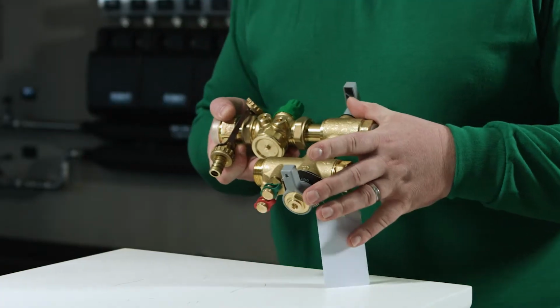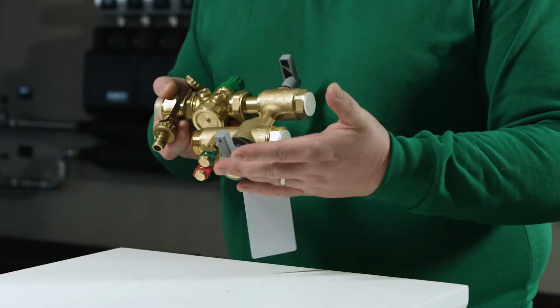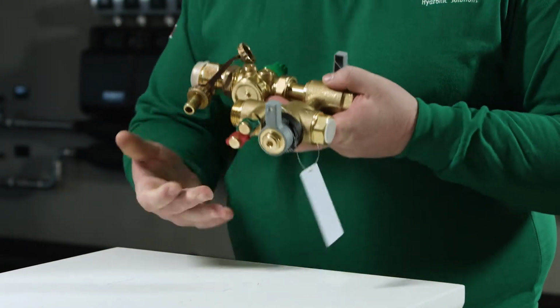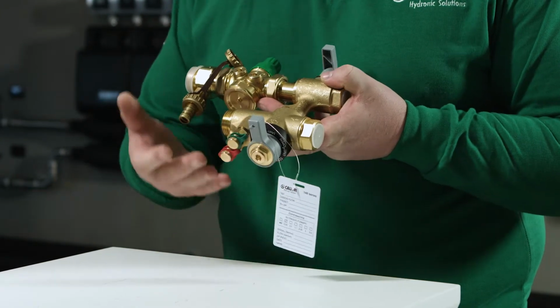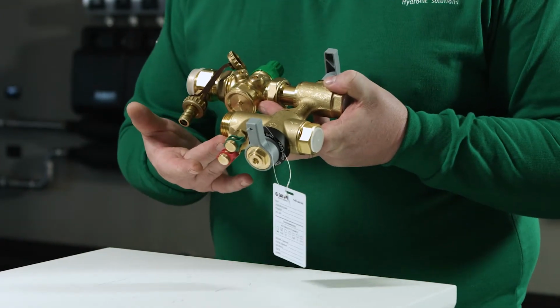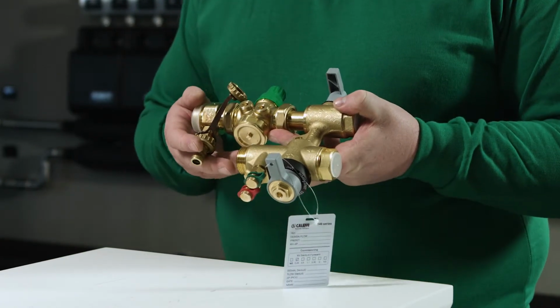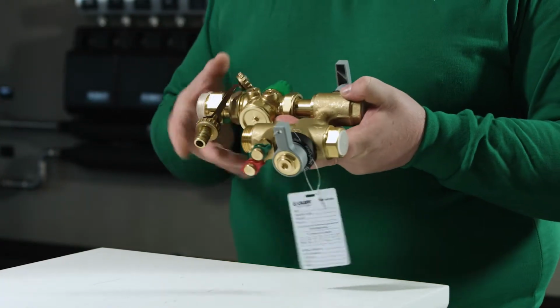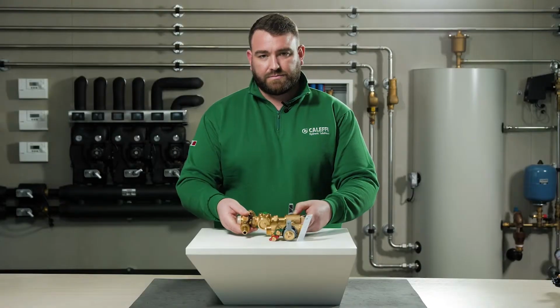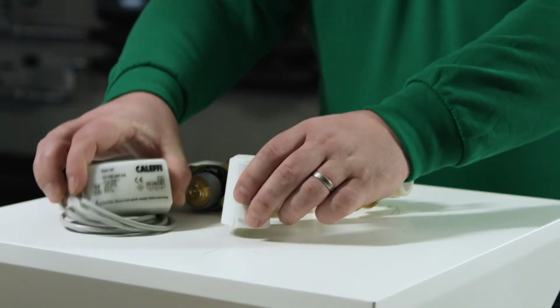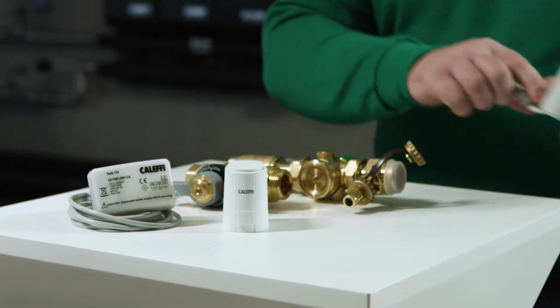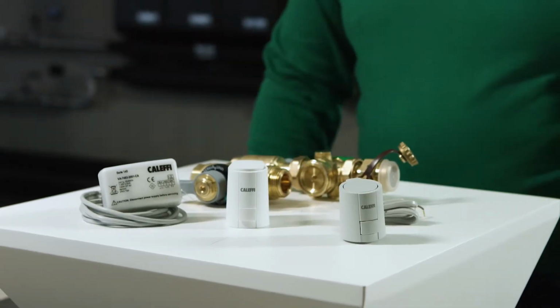Let's now talk about the features and components of the hookup kit. Here we have the shut-off valves for isolation of the terminal unit, the shut-off valve for control of the bypass line, an integral built-in strainer to prevent any dirt from entering the unit, a venturi profile for flow rate control within the terminal unit, 1 balancing valve to regulate the flow rate, and the control zone valve to regulate remote control. There is also the possibility to install actuators to the PICV. This allows remote control via the building management system. These include 0-10 volt linear actuator, or 24 or 230 volt on-off actuator.